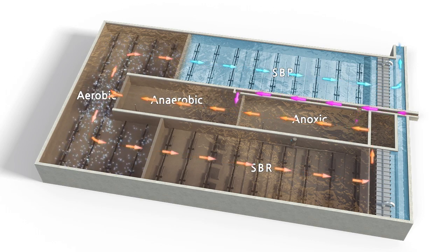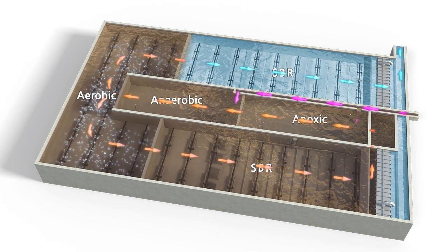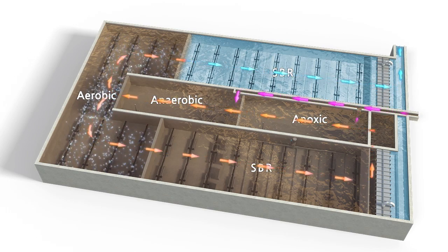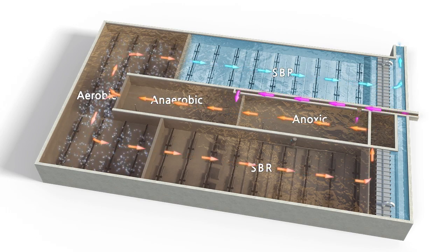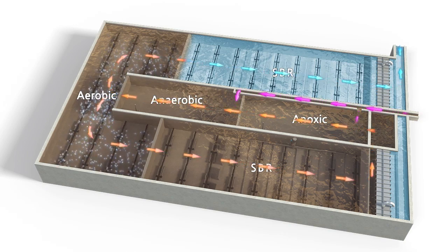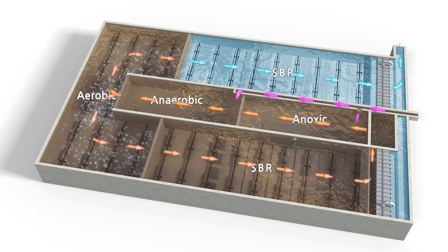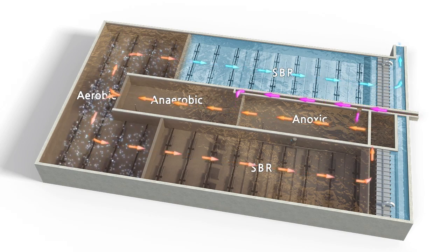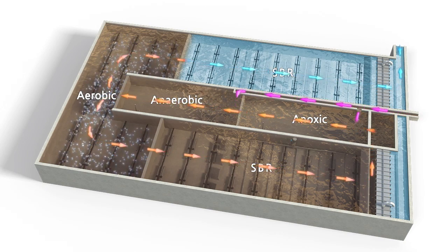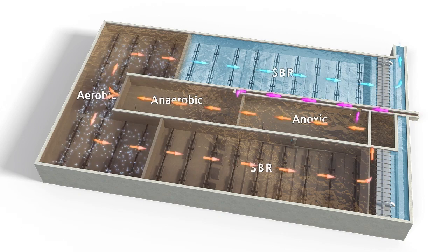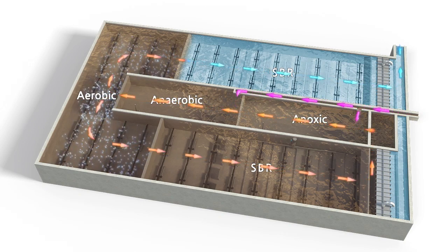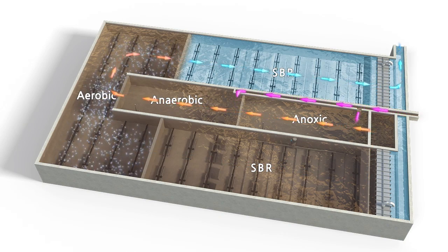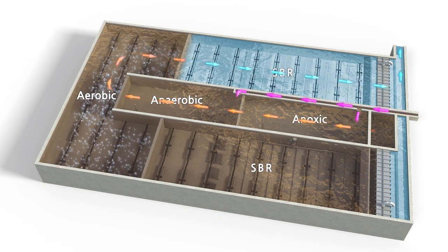Both SBR cells repeat alternately the discharge of treated water and reaction processes for 2 hours per cycle. After the solid-liquid separation is over in the SBR cell, the supernatant is discharged by the decanting system, and the settled excess sludge at the bottom of the cell is driven to the sludge treatment process at the desired time. At the same time, the other SBR cell proceeds with the reaction process.